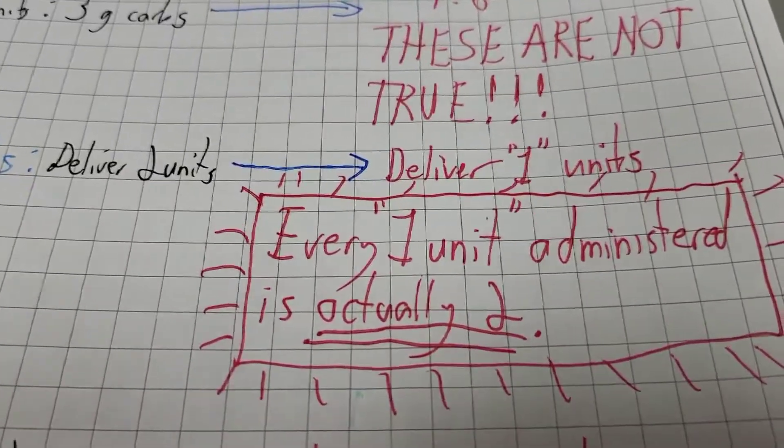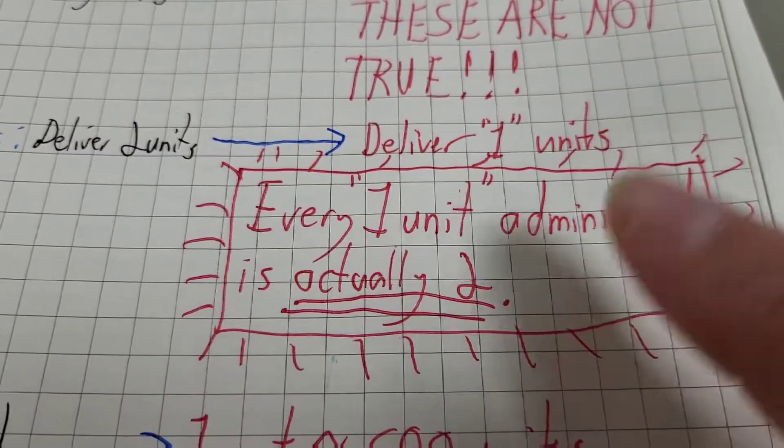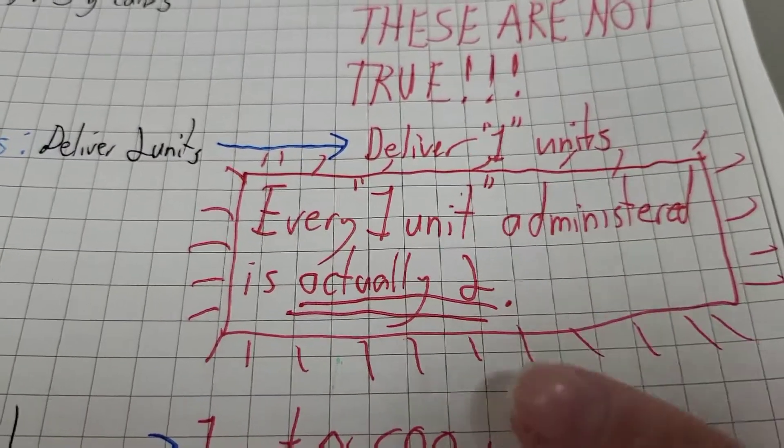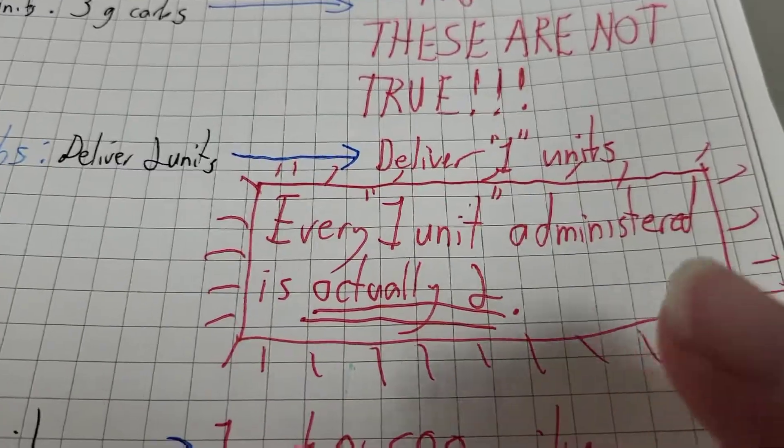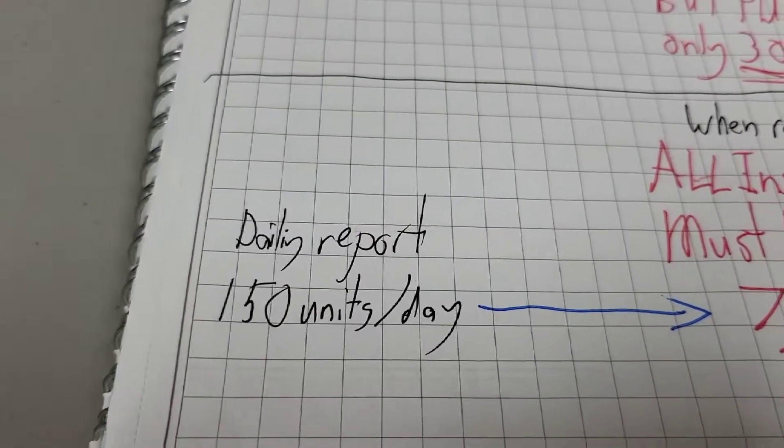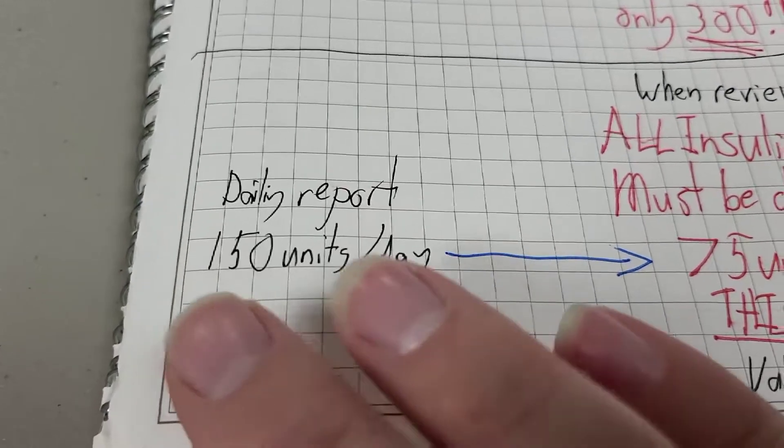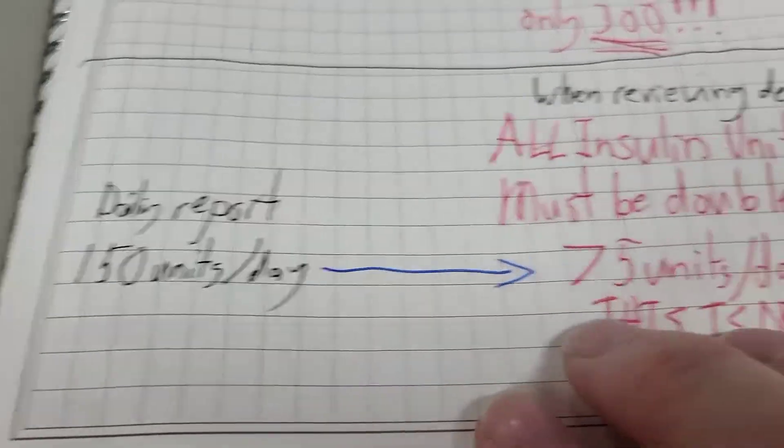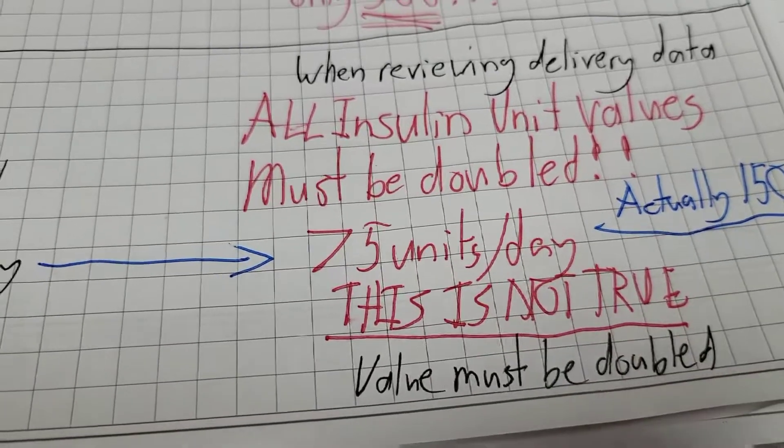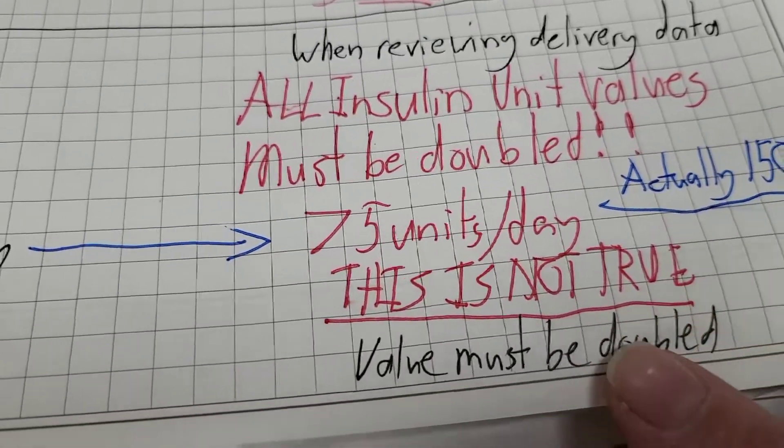This is very important. Every one unit administered by a pump containing U200 is actually two units. As I demonstrated, I use about 150 units a day, but the pump reports that I use about 75 units per day. That's not accurate. That value needs to be doubled.